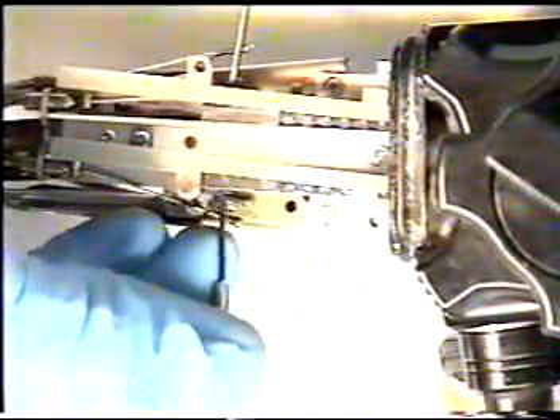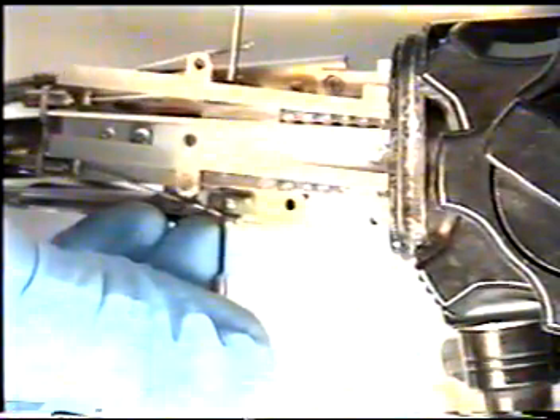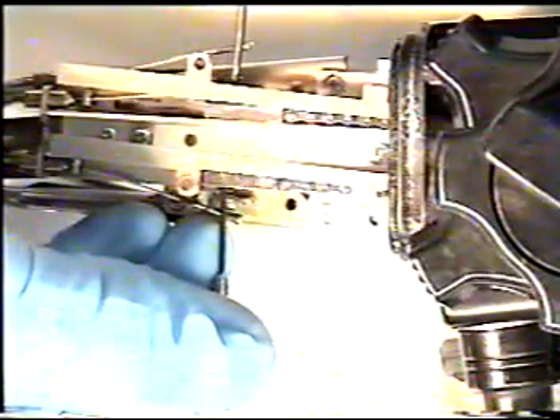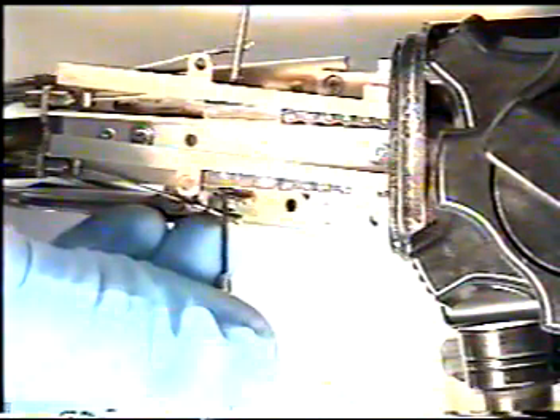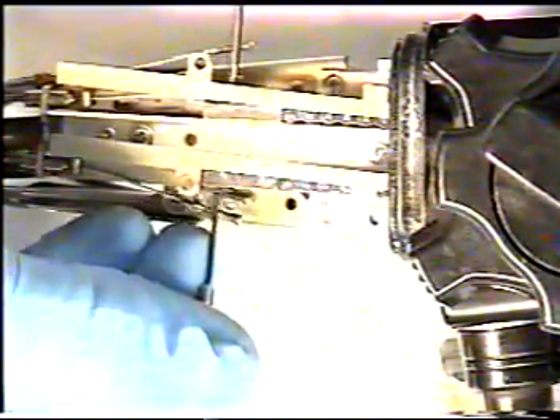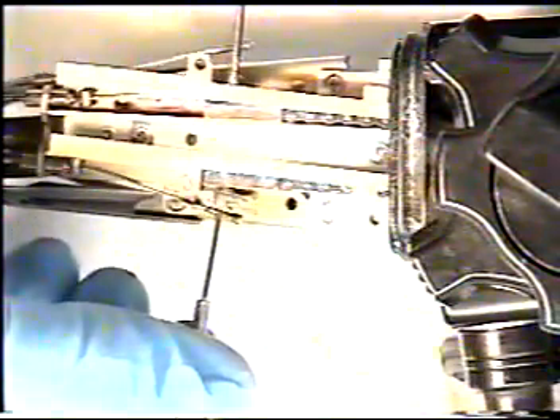You can view the blocks easier here, directly across from each other. Again, be sure that they are straight across from each other, the two screwdrivers and the notches. With this particular instrument and the play in the cables, we have come to the conclusion that the cable needs to be adjusted approximately 2 millimeters, meaning the edge of the control stopper meeting the notch in the chain guide block.